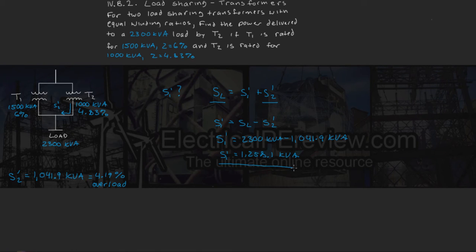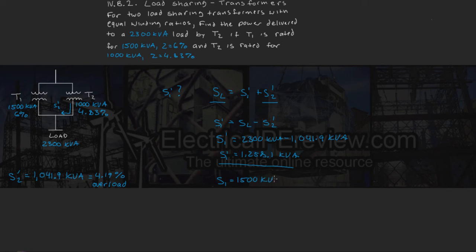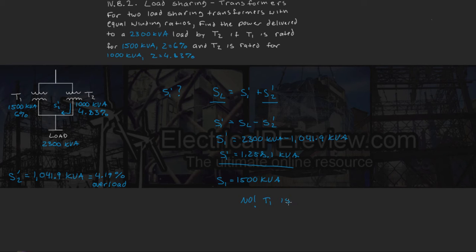Now, same question as before, is transformer 1 overloaded? Well, transformer 1's rating, of course, is 1500 kVA, and since we're only drawing 1,258, the answer is no, T1 is not overloaded.